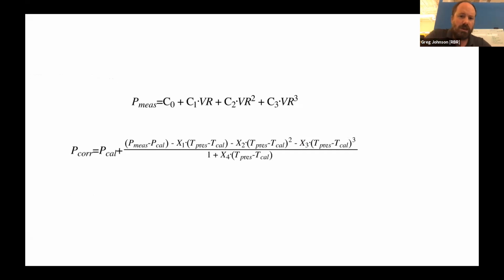So next equation for today, this is pressure, as you can no doubt deduce. And so our C coefficients are those that we use for direct coefficients in a polynomial typically, where we're calibrating. We also have X coefficients, and X in our mind stands for cross, which means cross-channel correction factor. So the first equation is that if we just want to make a very simple measurement of pressure, we can calibrate in a single temperature tank against those voltage ratios that I was talking about before using a cubic.